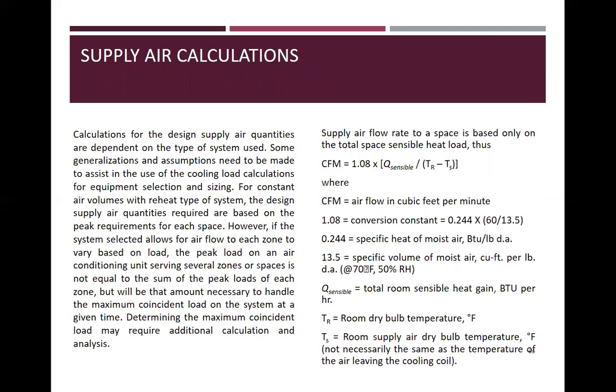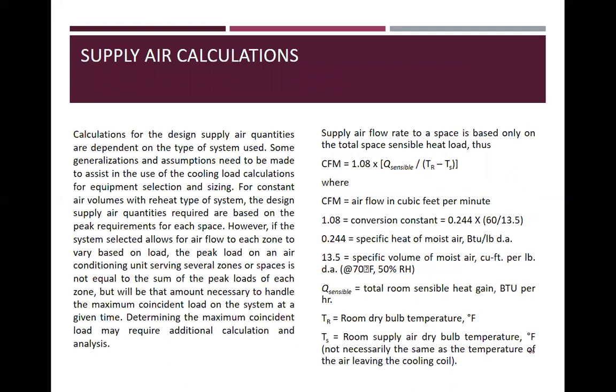Calculation of supply air. Now, next is the supply air calculation. Calculations for the supply air quantities are dependent on the type of system used. Some generalization and assumption need to be made to assist in the use of cooling load calculation for equipment selection and sizing. For a constant air volume type of system, the design supply air quantities required are based on the peak requirement for each space.